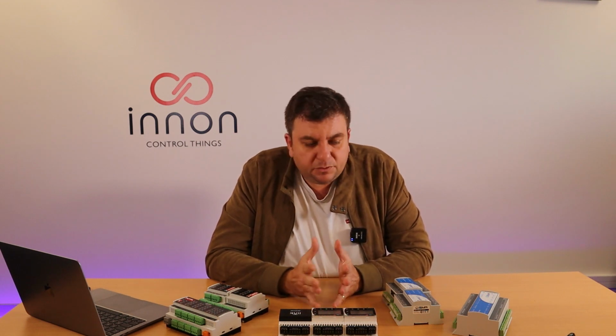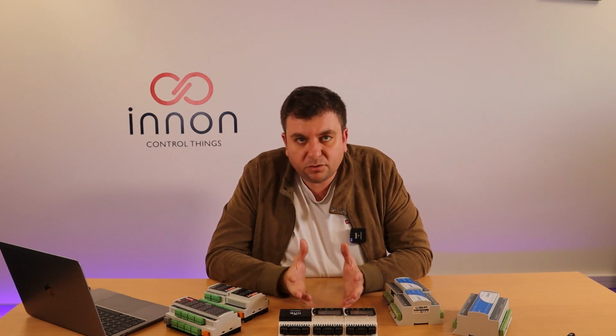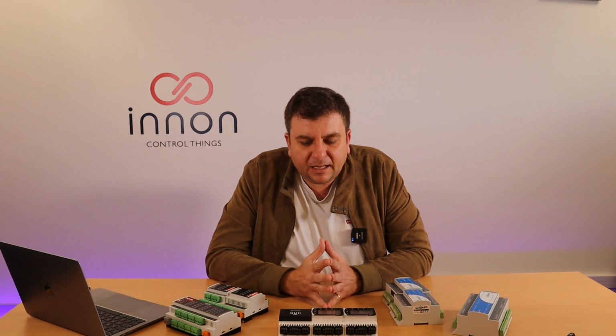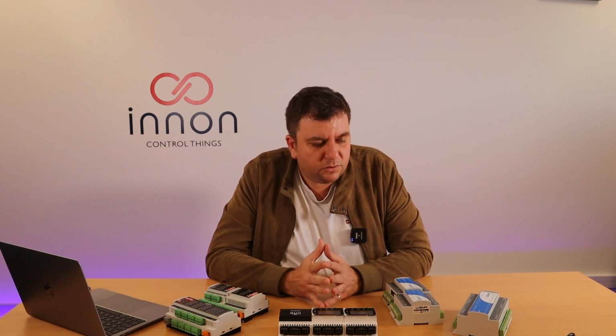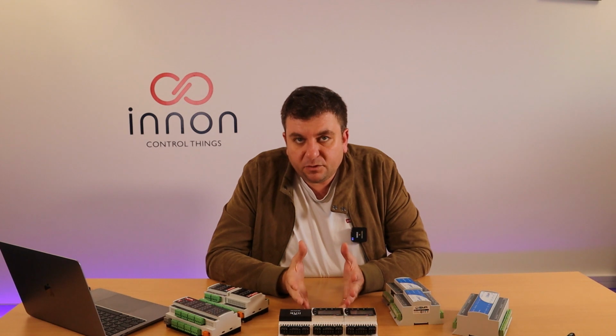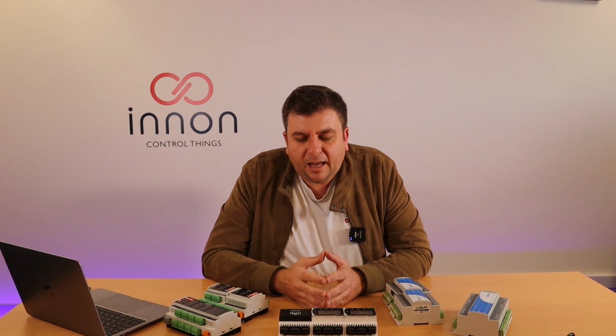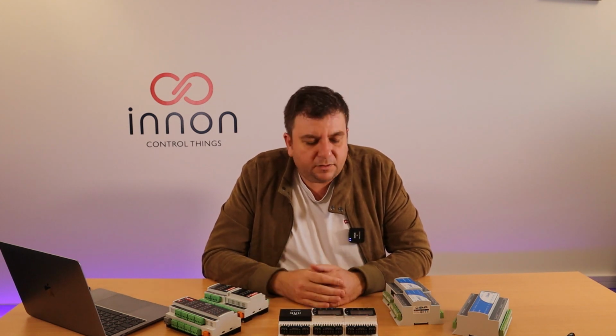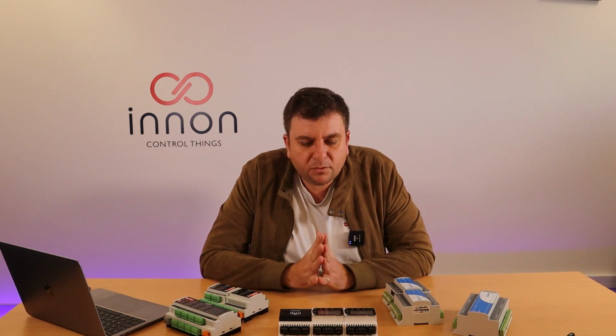Other features which they share in common are the watchdog. The watchdog is maybe not so well known a feature, but I think without a watchdog, an Open Protocol I/O module can't be really functional, because a watchdog enables the I/O module to sense if the main system is offline. And so in a circumstance like that, it just shuts down or goes into some sort of default position. So you lose connection with the main system, and then you may decide to switch off a pump or turn off a light and so on. So that would be the main common features of Open Protocol I/O modules.